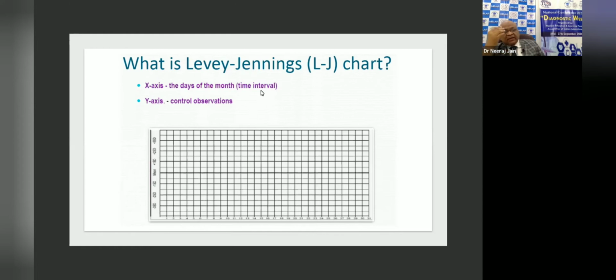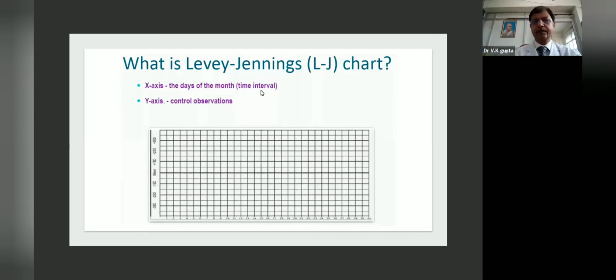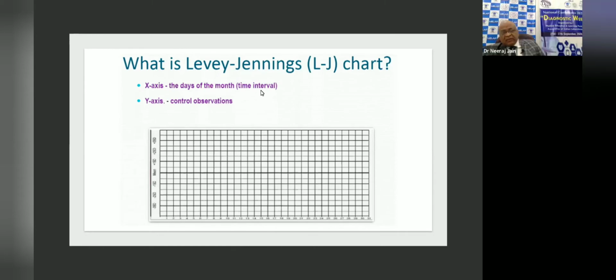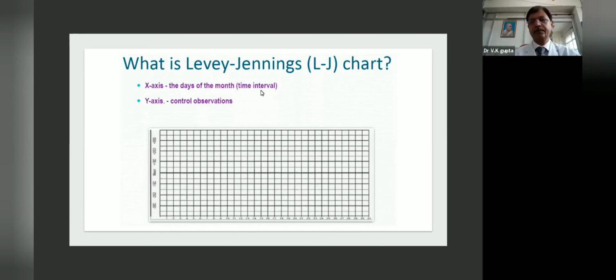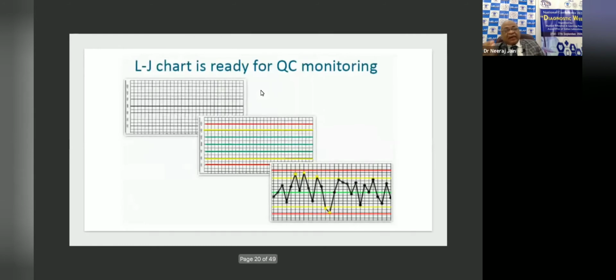Suppose we are running one level of control twice daily, one in the morning, one in the evening. For the different analytes required, we prepare a different Levey-Jennings chart. For each different level of control, we prepare a different Levey-Jennings chart. But if we are running the same level of control for a particular analyte more frequently, say twice in a day, the same Levey-Jennings chart will work. We plot our daily observations on this chart, and when these points are joined, this is called a Levey-Jennings chart.